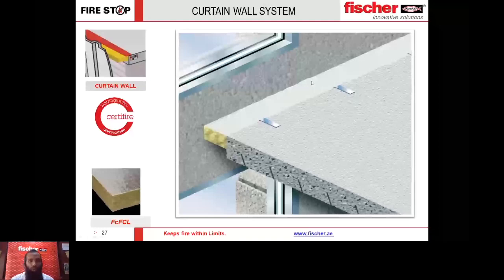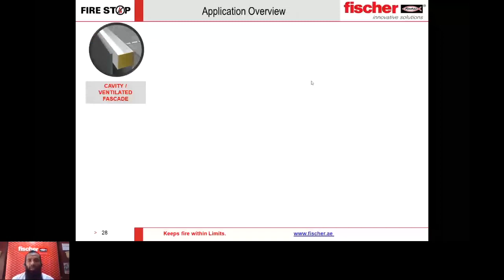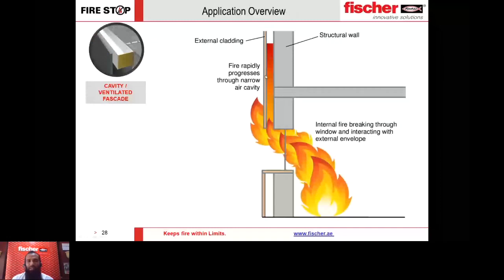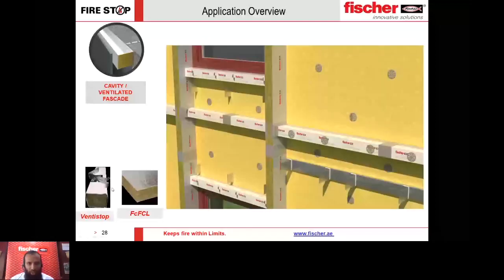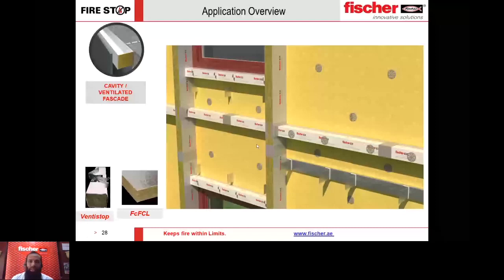There is another type of facade — stone facades. These facades have a ventilation gap behind them. During a fire, this ventilation gap behaves like a chimney, allowing fire to spread between floors. We need fire stopping in this zone as well, dividing it into different compartments. We have something called Venti Stop, which ensures you retain the ventilation gap needed but during a fire it expands and closes the gap, stopping fire spread.